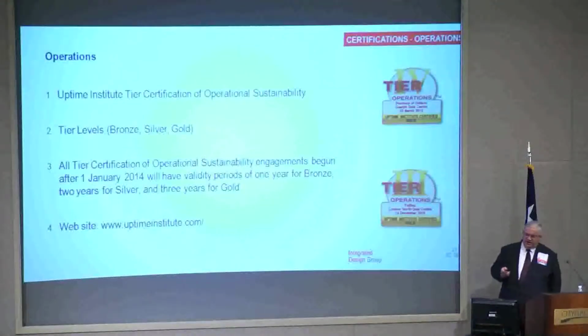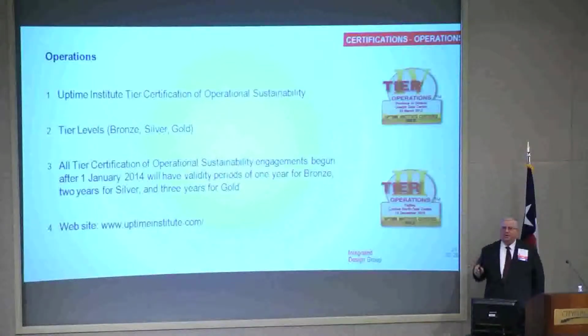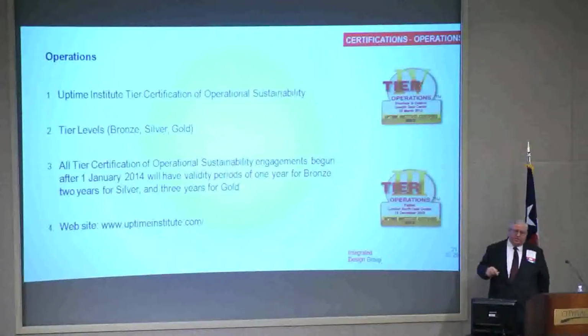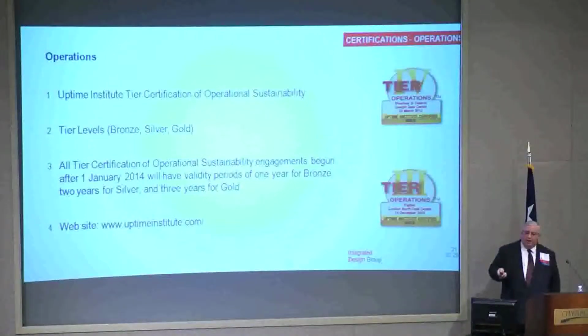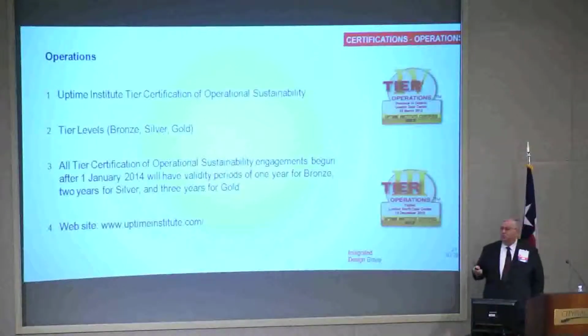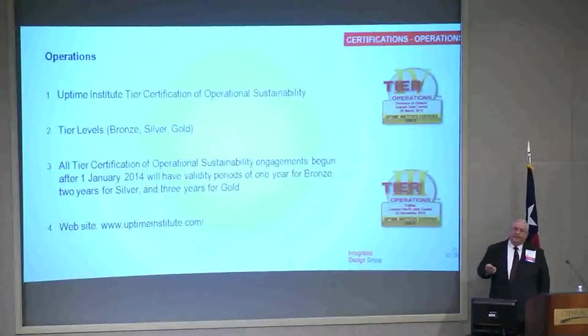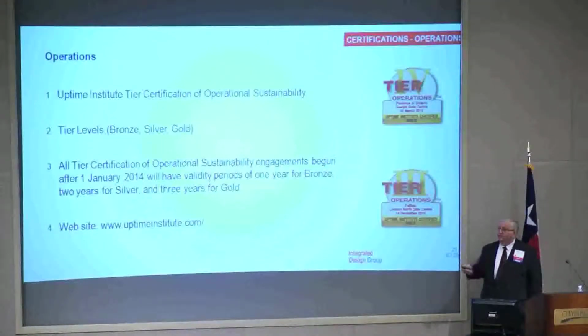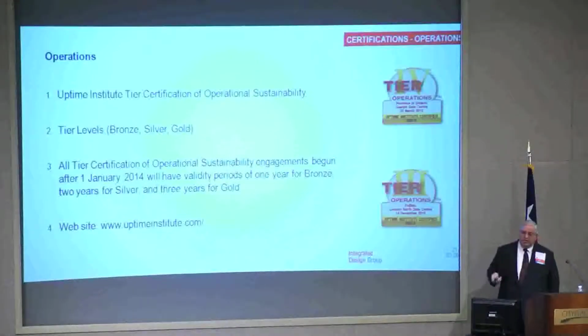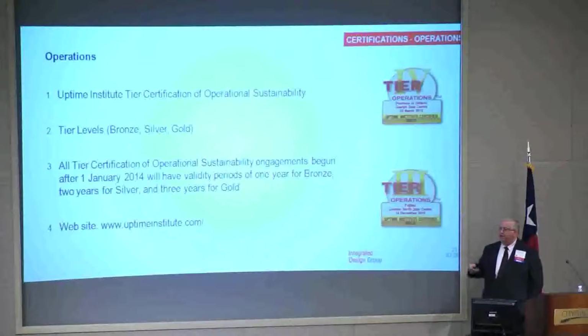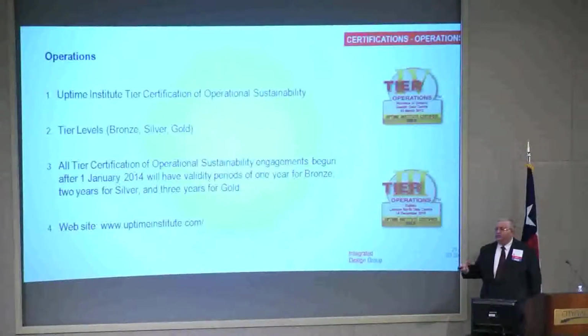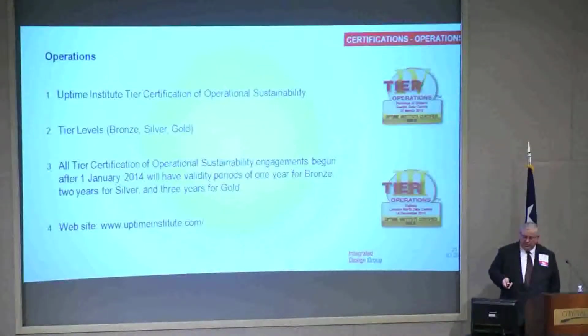Operations is another certification that Uptime has come up with. So rather than the reliability, they don't touch all the other issues. To deal with that, they've come up with an operations requirement, which can be gold or bronze or silver. And they go the extra step for a tier 3 rating with Uptime. You can get away with that by using one UPS power path and one non-UPS power path. And that meets their requirement. We don't see that very often, but that does meet their tier level. This operational requirement, if you put in 2 UPS paths to your equipment, you get a higher tier level operations, so you get a tier 3 gold versus a tier 3 silver. It works, that's the way they work it.